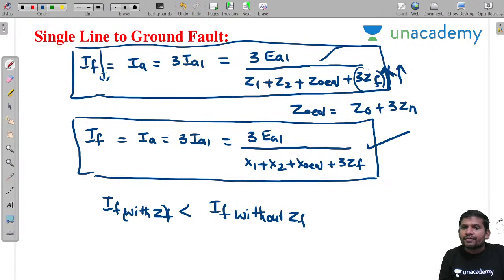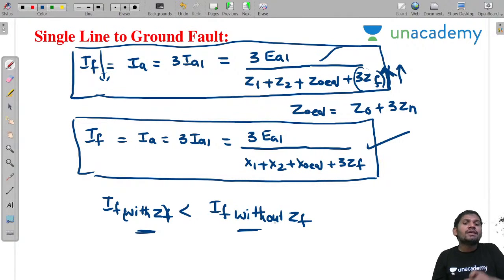Without any fault impedance, we get more fault current. If there is a fault impedance ZF, we get less fault current. Because of this ZF, the fault current is limited and reduced.